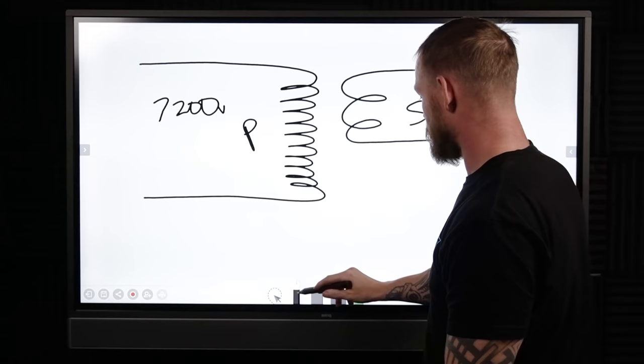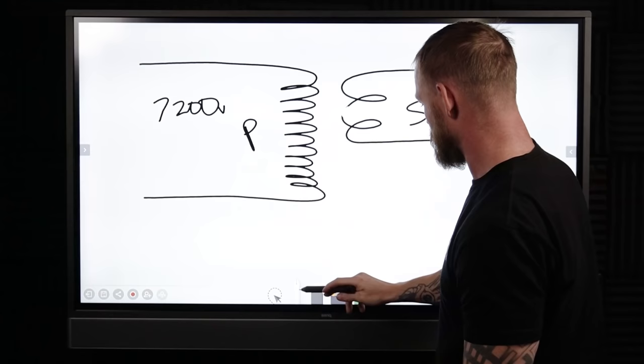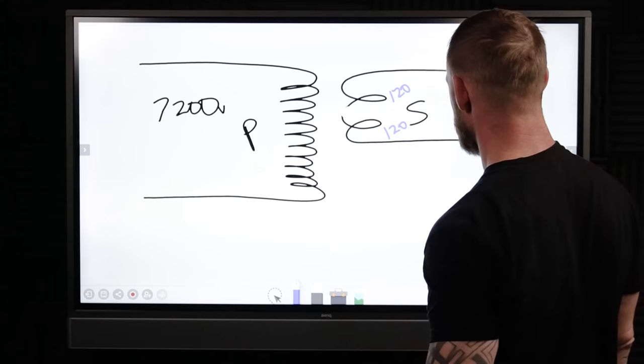Let's say in the middle of this coil we tap in the exact center and we come out with a conductor. Well, if there's 240 volts between our two hots, then we've got 120 volts between each hot and neutral, but still 240 volts between them. So this is what we would call the neutral point.